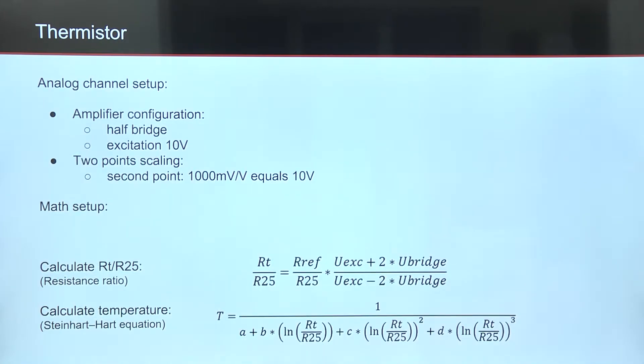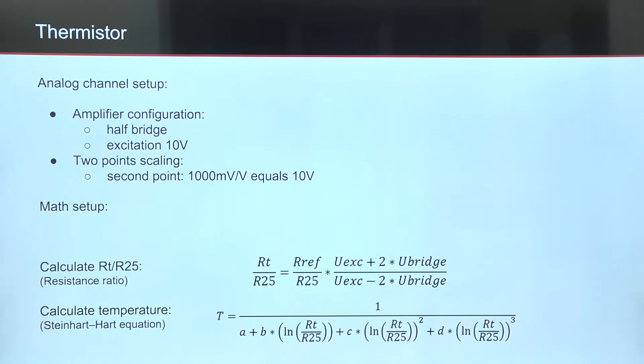In DeweSoft, we have to set up analog channel to half-bridge configuration and set excitation to 10V and fix two-point scaling from 1000 mV equals to 10V.